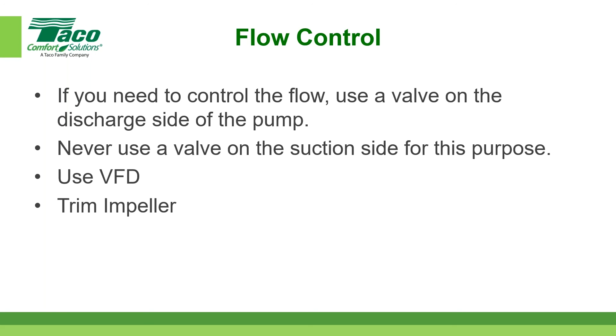Some ideas about suction valves. There are different types, right? Just like that tidbit Rich said about the pressure gauge, maybe a gate valve is the best one to use, because it doesn't add any, or adds very little, resistance and can provide a tight shutoff. The less resistance we can put on a pump, the better it helps the head loss you're talking about once you start doing your calculations. Many times butterflies are used, but they do provide some resistance, and you have to take that into account. I'm not saying it's a big deal, but it's something to consider. And then potentially you get some hangups, which is not good at all on the suction side.